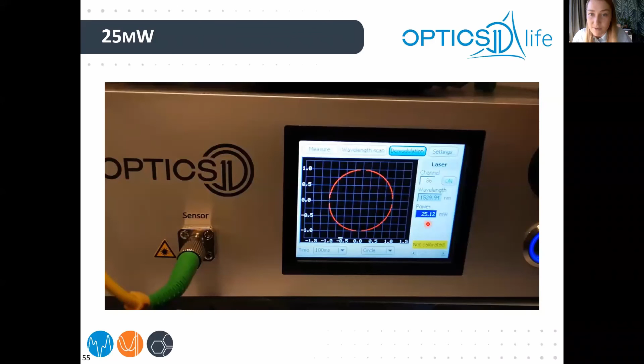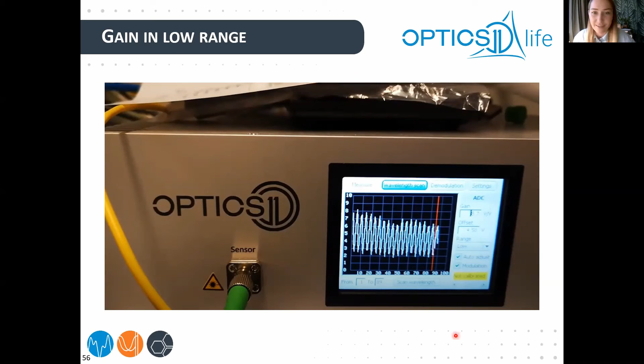Now you can increase it to the maximum one, to the 25, and then you repeat the wavelength scan, and then you will see that the range is low. And what it means is that the signal to noise ratio will be much better. So there will be less noise and all the measurements will look better. So that's a little trick. We are going to make this feature automatic, so that the interferometer will just decide by itself that it needs to change the laser power. But until we have that feature implemented, you will need to do that manually.